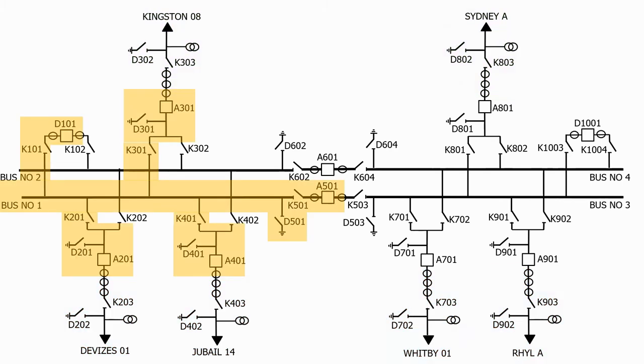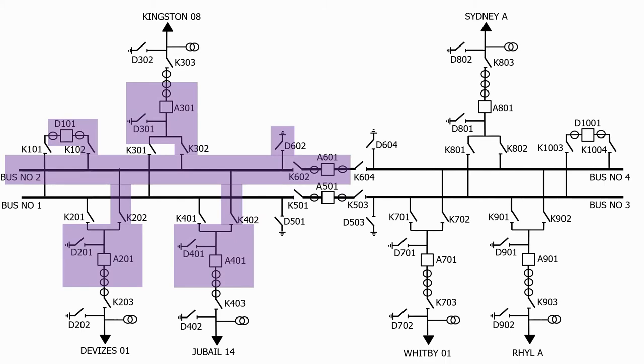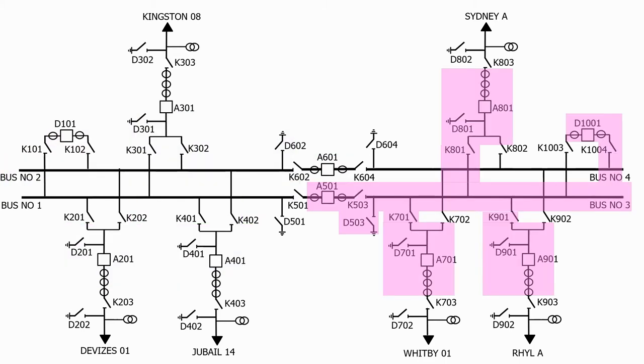As we can see on the bus coupler circuit breakers and bus section circuit breakers we use the outermost CT so that we can overlap with the protection zone on the adjacent bus bar. Let's now do bus bar number 2, bus bar number 3 and bus bar number 4.